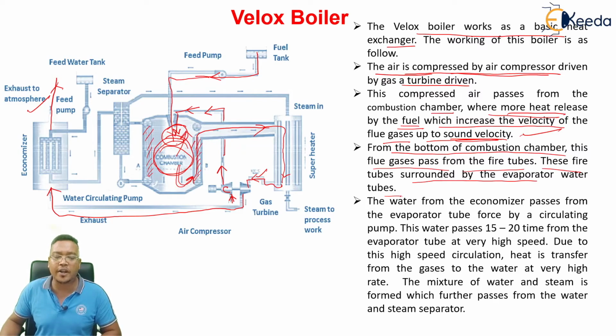Now let's see the water and steam circuit for the Velox boiler. This is the feed water tank, and water will come from the feed water tank and, through this feed pump, it will be sent into the economizer, and then through the economizer it will be sent into the steam separator. From the downcomer, the water is sent into the evaporator tubes with the help of a pump. That's why it is a forced circulation boiler.